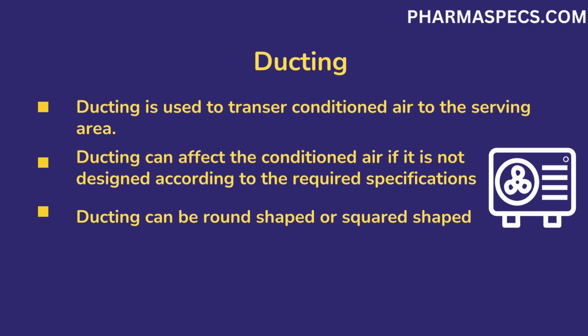Ducting. Ducting is another critical part of pharma HVAC system. It is used to transfer the conditioned air from the AHU to designated area. Ducting can affect the performance of conditioned air. If it is not properly designed and maintained, it can contaminate or change the airflow characteristics before reaching its area.